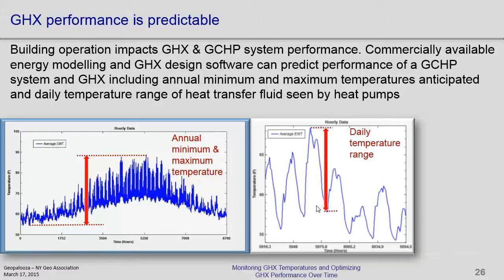There's a company out of Michigan that is automating this system. They plug the energy loads into the software that they've developed or that has been provided by an engineering firm or whatever. Here's what the temperatures are expected to be, and then they plug an energy meter onto the ground heat exchanger, and if it's off target, they'll run the fluid cooler or a boiler to compensate, or whatever they've got. We've done one where we've integrated a horizontal ground loop with a vertical ground loop.